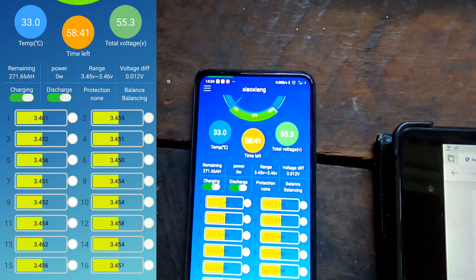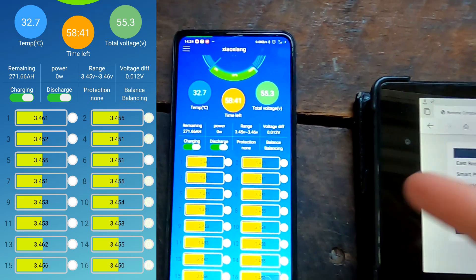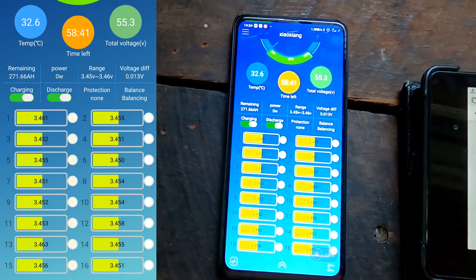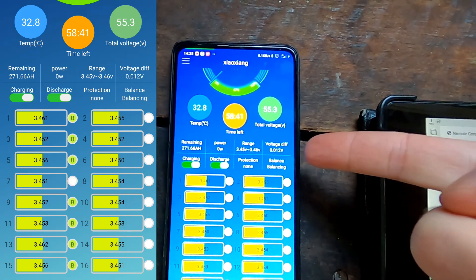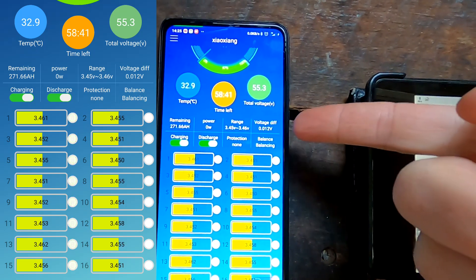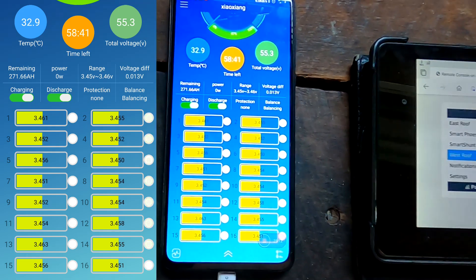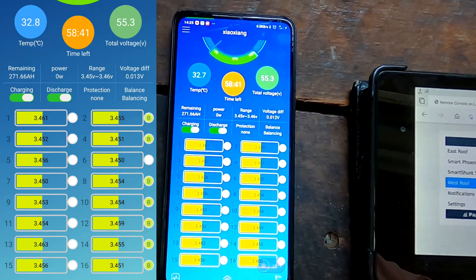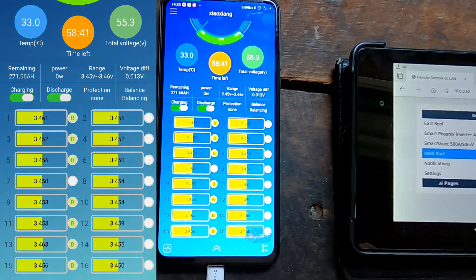After about 25 minutes we are still absorbing at 55.2 volts. Deviation is now 13, 11, 12 millivolts - that's pretty good. It came down from 45 millivolts to around 10-12. They're all balancing apart from number six - there's always one. This seems to have worked.